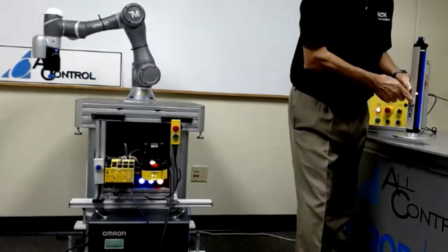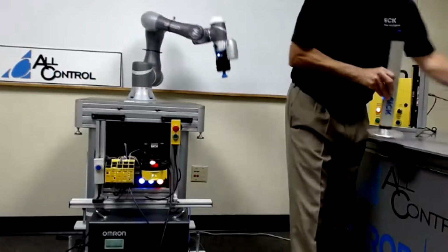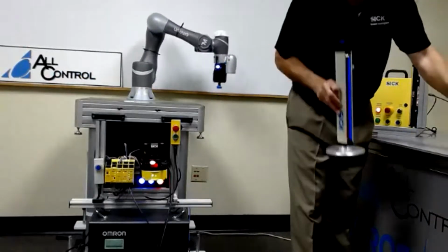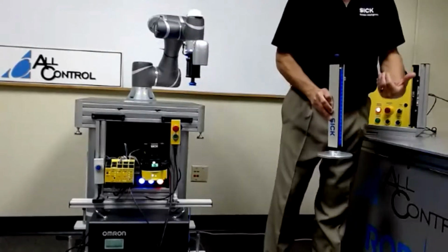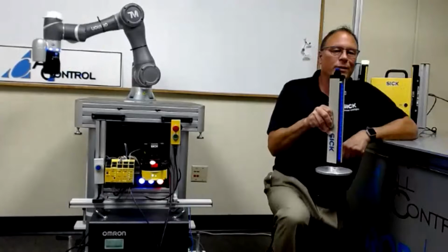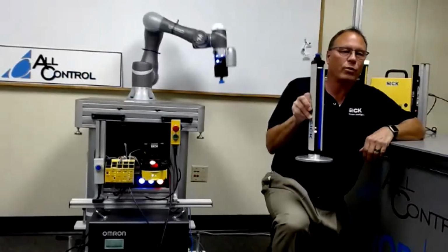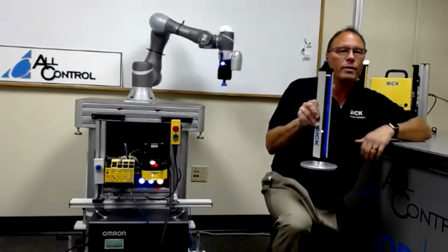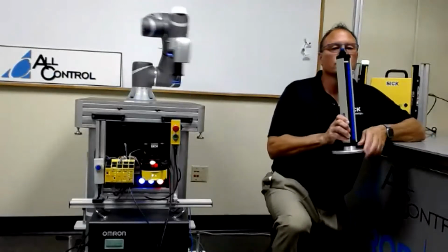So this is what I call a laser finder. It's called an alignment bar. But what it's designed to do is to tell you where your laser is. Our laser scanners can go out 9 meters. Well, at 9 meters, if your scanner is just sloped a little bit, you may not be able to find where your laser beam is. Remember, it's infrared.